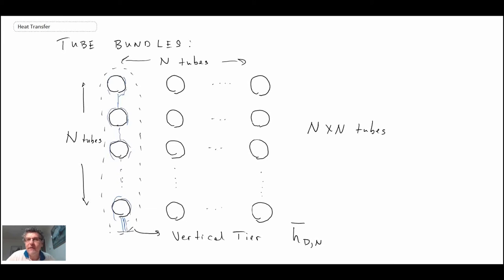We would have the convective heat transfer coefficient for n tubes in the vertical direction. And in order to compute that, what we do, we begin by computing the convective heat transfer coefficient for a single tube. And then we multiply it by the number of tubes in the vertical direction, raised to the power minus one-sixth.